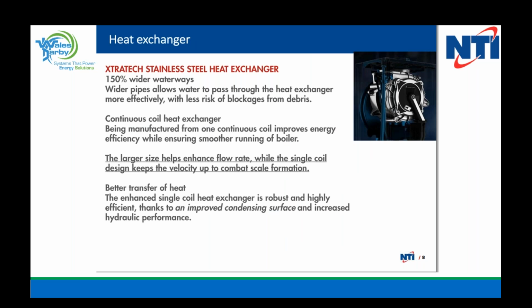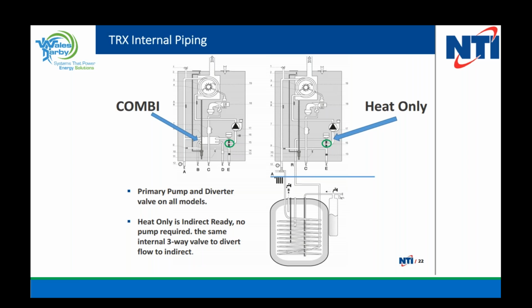Go forward, please. All right, so it's basically a 150% wider waterway. And again, it's a continuous coil, and we get a better heat transfer because we've improved the condensing surface and we've increased that hydraulic performance. Move forward, please. So here's the inside of it, and both the Combi and the heat only have the same diverter valve. There is the internal pump. That is an ECM pump made basically by Taco. So it has a Taco ECM pump, very strong, very powerful. When we're in heat only, it's indirect ready, so the diverter valve changes position and we drive flow into that indirect. On the Combi side, you can see the small heat exchanger that's in there. And again, when we're making domestic hot water, the diverter valve will change its position and divert flow to the heat exchanger.